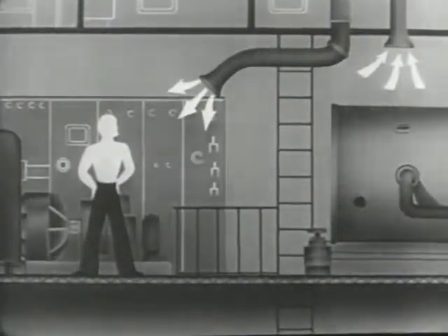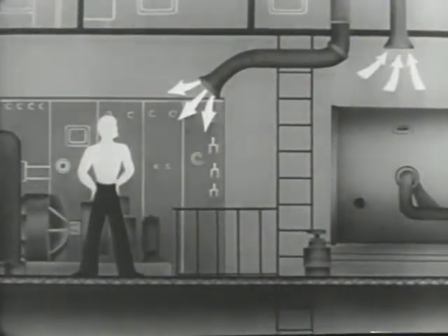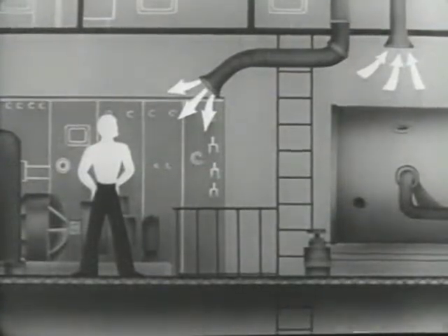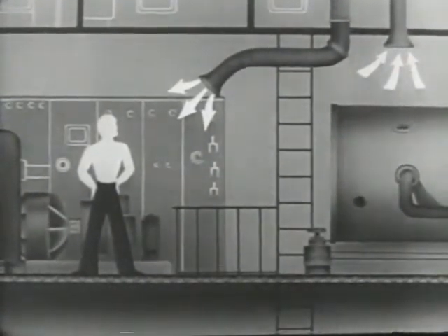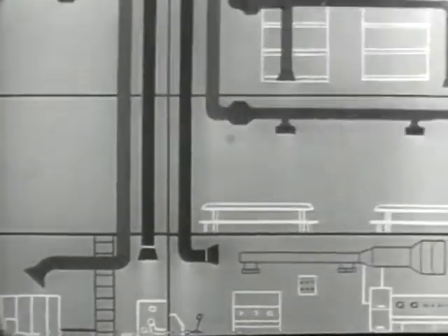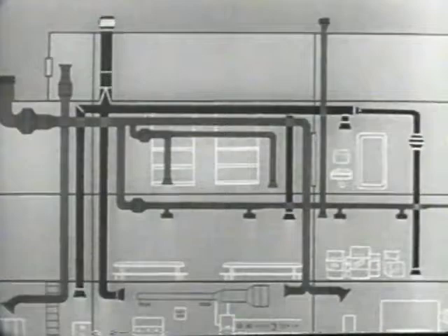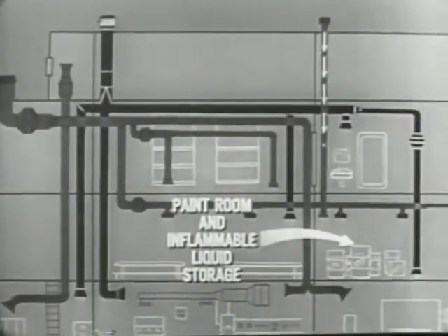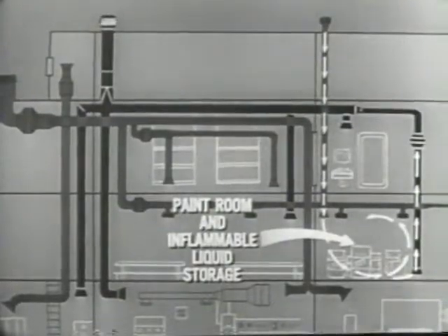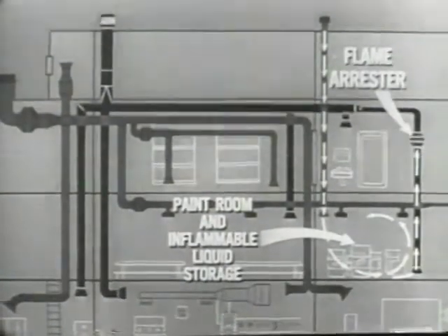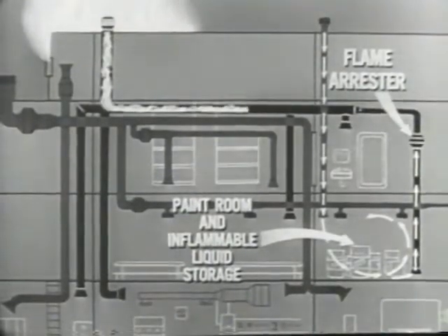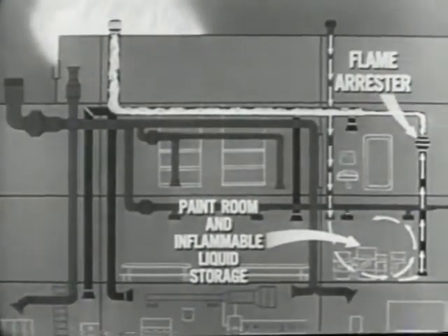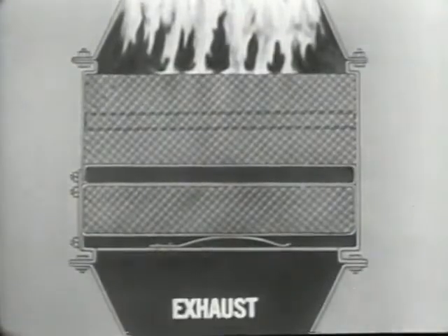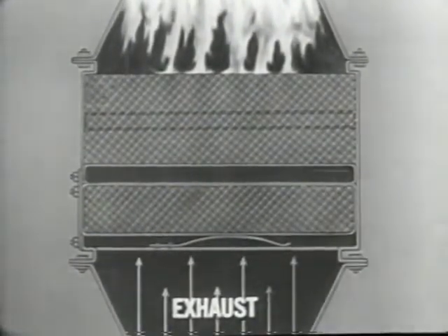Machinery spaces are provided with a greater rate of exhaust than supply, creating a slight negative pressure which prevents hot air from escaping to nearby living and working spaces. The operation of supply and exhaust fans should always be coordinated to ensure this negative pressure. In compartments where combustible vapors present fire hazards, exhaust ducts are equipped with flame arresters. If fire breaks out adjacent to the ventilator or weather opening of an exhaust system handling combustible fumes, and flames spread back through the ductwork, the arrestor will prevent the passage of flames into the space.